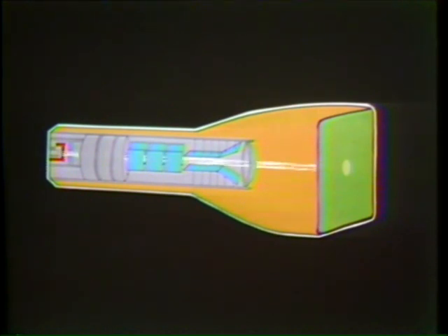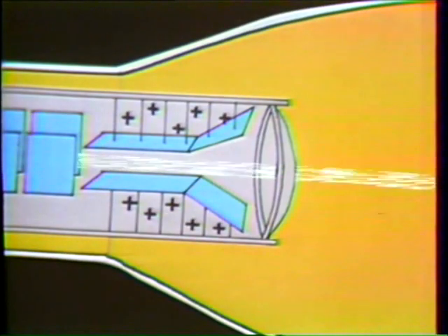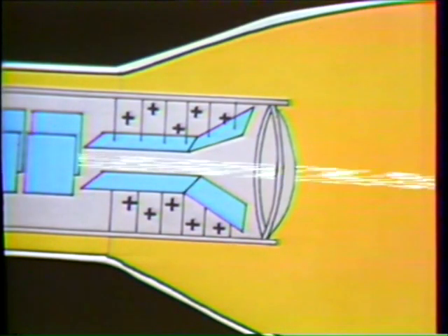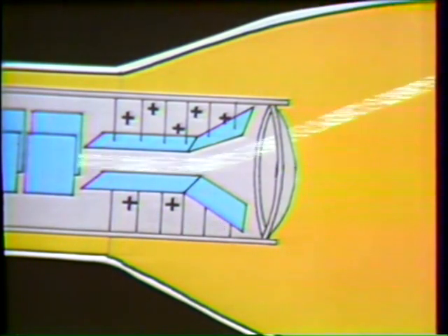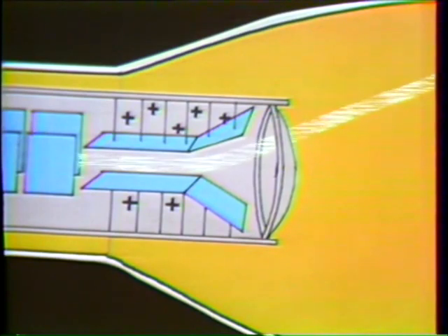Electrons in the beam have a negative electrical charge. As the beam passes through the gun, positive charges are applied to metal plates called deflection plates. One pair deflects the beam vertically and one pair deflects the beam horizontally. The beam will move toward the plate with the most positive charge. When the charges on the opposing plates are changed, the electron beam is moved across the screen. That's how the pattern or trace is created.